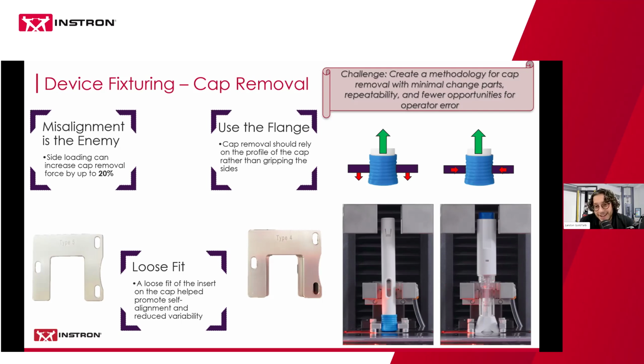The ISO standard is extremely vague in how it describes its testing, unlike other ISO standards where they're extremely explicit about how you perform the test and how the fixturing should look. The standard is vague purposefully because they don't want to stifle innovation - they know devices are going to look different and don't want to force people into a specific design choice because of how the test is explained in the standard.